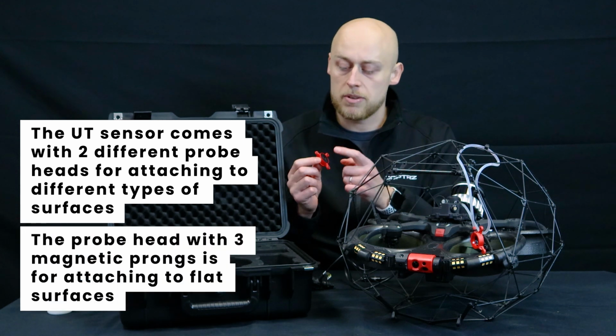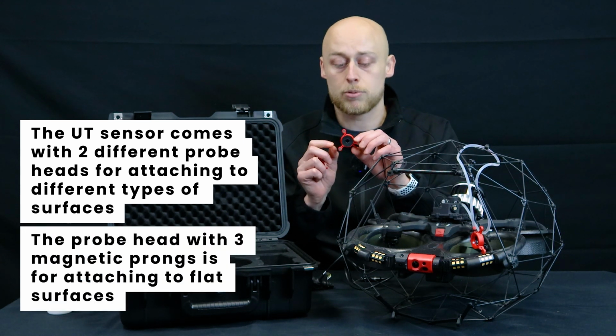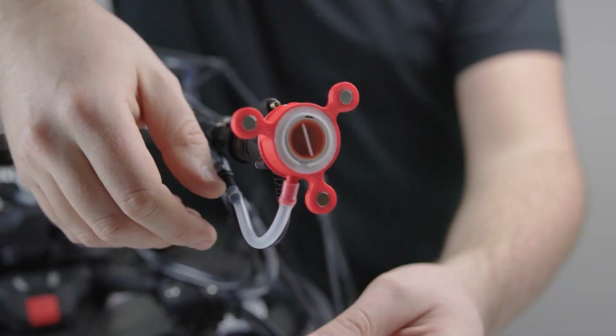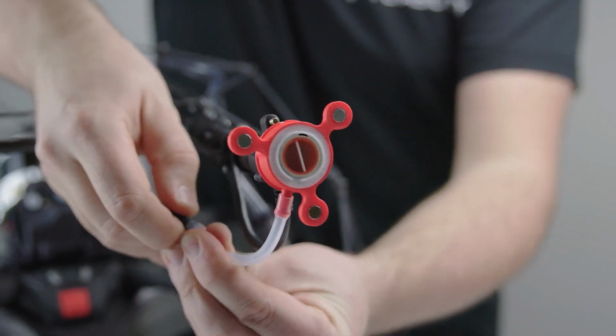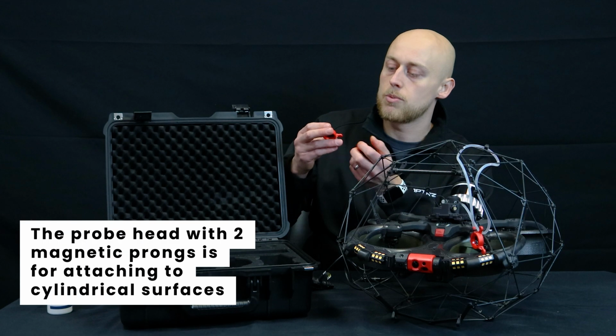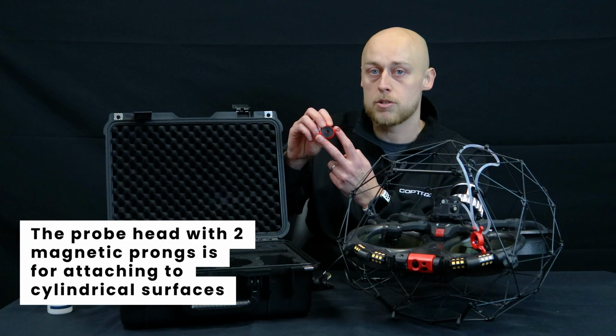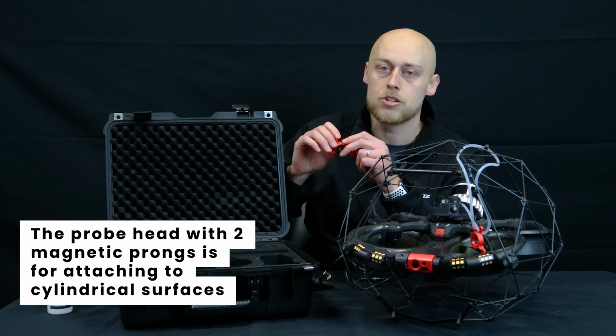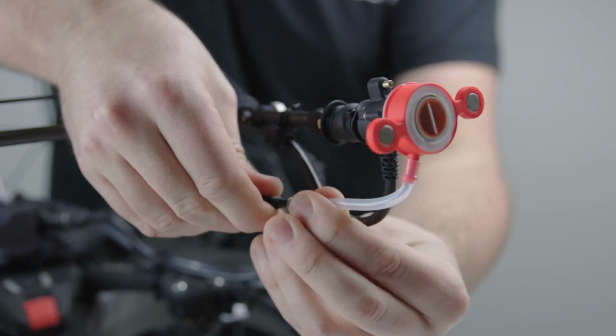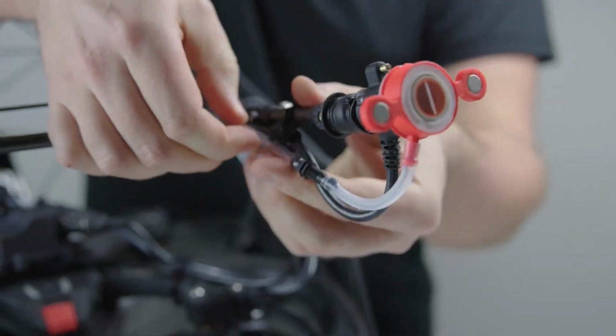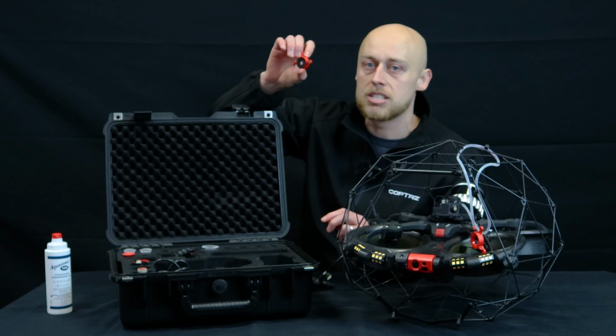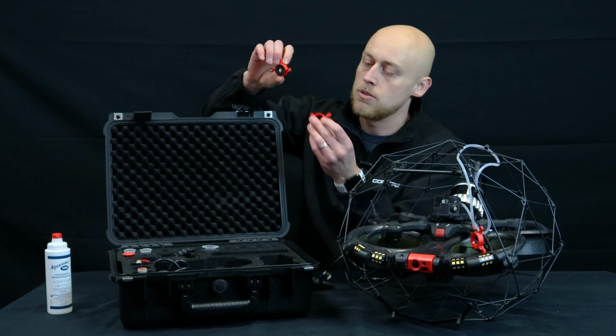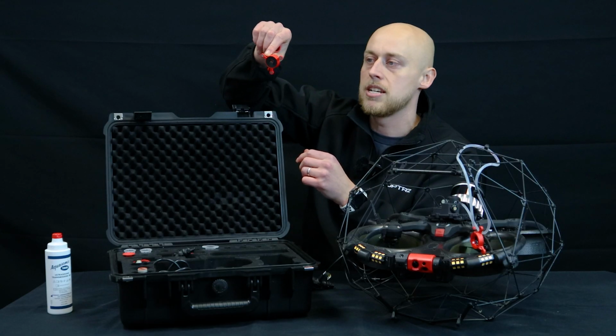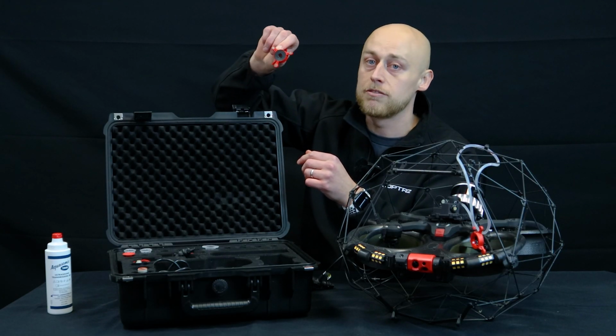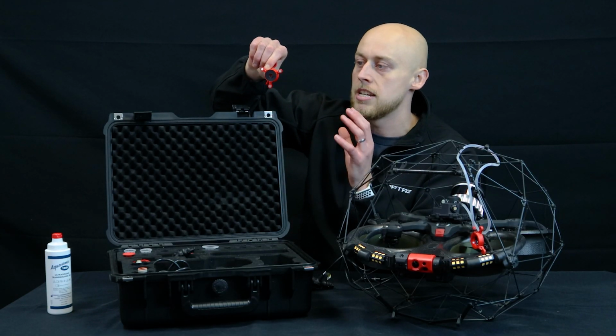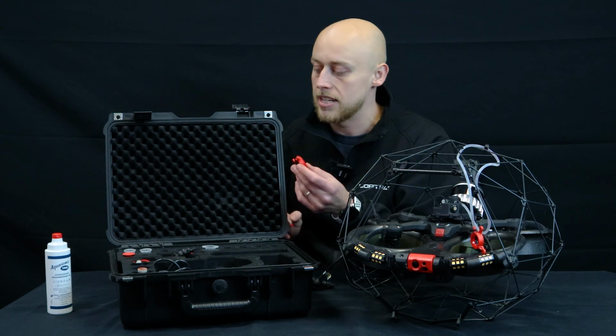You get multiple different probe heads which allow for different surfaces. This one has 3 magnetic prongs on the probe face, which allows you to stick to flat surfaces better, whereas we have a 2-prong approach with this one. This will allow you to attach to smaller pipes, because you want something that gives you the best data possible. Whereas with a 3-probe head on a thin pipe, it may rock back and forward and won't attach all 3 magnetic interfaces.